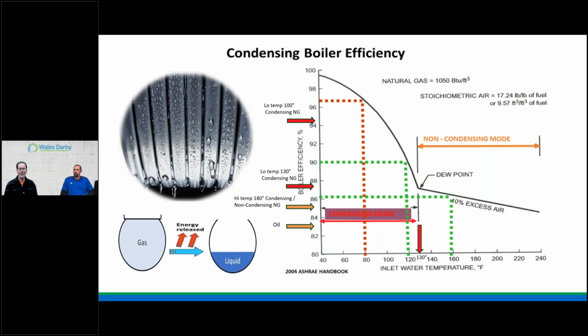But imagine I do have a system that now runs at 120-degree water. I've understood the envelope of the building. I did a heat loss. I sized my emitters to maybe be oversized so that when I give it low temperature water, it actually still emits the BTUs required. So now I have a 120 design, but yet I have a 20-degree delta T, and now my return water back to the appliance is 100 degrees. So imagine my brain is saying, oh, I live in 180, I live in 180. Now you tell me I need 120, or yet I have return water of 100. I'm out. People are turning off this webinar right now. They're afraid. They don't want to change. They're set in their ways.